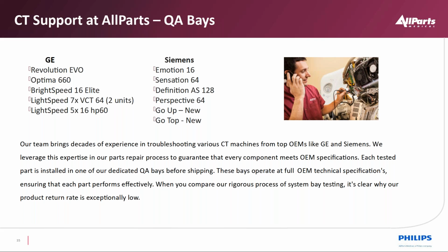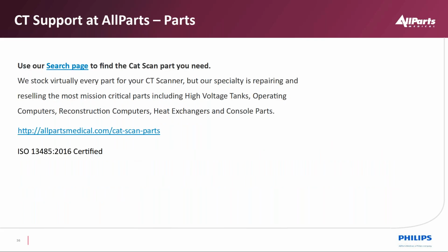That's why we have the diversity of the number of machines we have, and we get to leverage them for both repair and also testing and validating tube providers that provide X-ray tubes to make sure they meet OEM specs. And then that way we can put them on a shelf, knowing that they'll operate and reduce downtime in the field. So Philips multi-vendor uses parts from AllParts as well as third parties. So we find it very effective to reduce the DOA rate. Sometimes things are damaged at shipment, but our DOA rate is very low at AllParts.